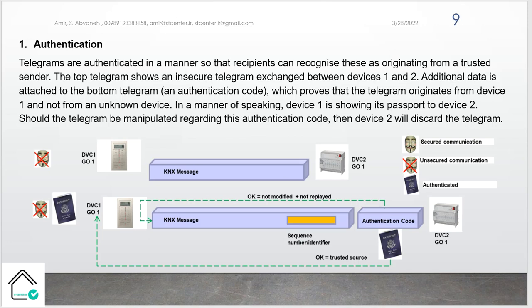First, authentication. Telegrams are authenticated in a manner so that the recipient can recognize these are originating from a trusted sender. So any sender cannot send the data, only the trusted one can send data in KNX Secure. The top telegram shows an insecure telegram exchange between device 1 and device 2. Some message is transmitting, and if somebody like a hacker wants to send a message instead of this keypad, he can do that.